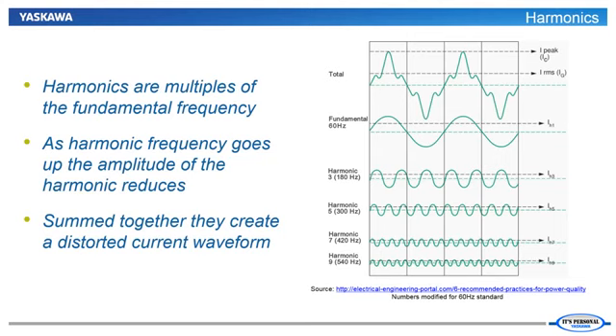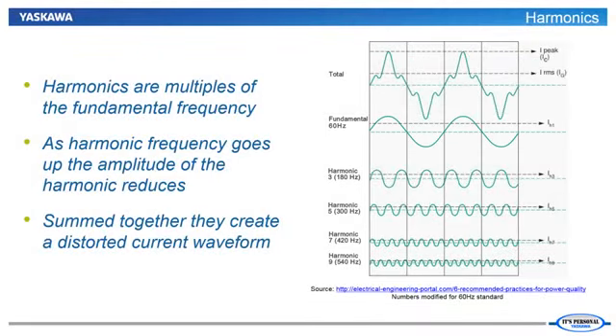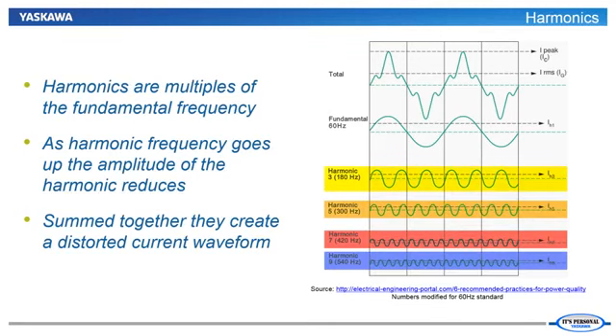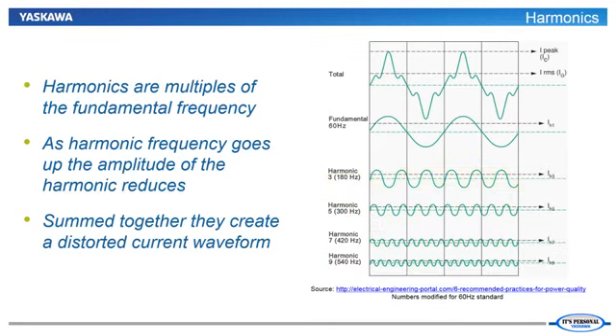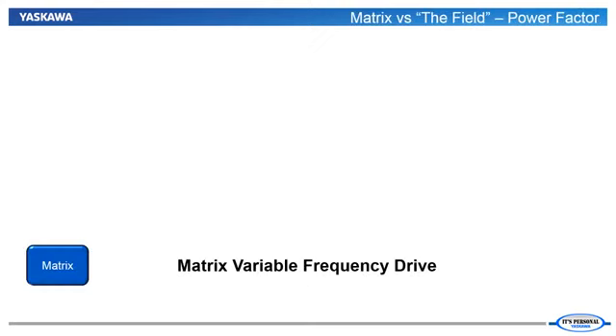Since we have brought up the topic of harmonics, let's try to give them a conceptual definition. Harmonics are, in a simple sense, just multiples of some fundamental. Since we are speaking of AC current, then harmonics are sine waves with frequencies that are some multiple of the fundamental frequency. In the graphic on this slide, the fundamental current frequency is 60 Hz. Also depicted are representations of the 3rd, 5th, 7th, and 9th harmonic of a 60 Hz fundamental waveform. Of course, standard VFDs and matrix drives are not the only choices when it comes to users concerned with mitigating harmonics and improving power factor.